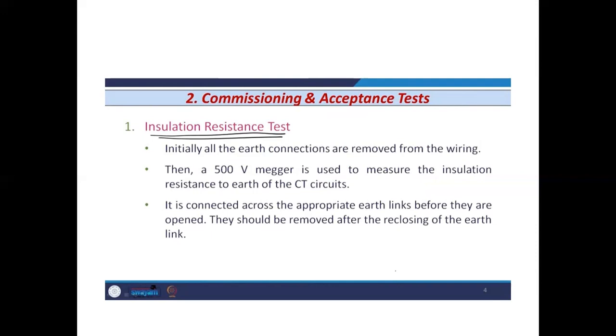Insulation is very important for the protective devices and the equipment. If proper insulation is not provided, it may cause electric shock to the operator, so proper insulation is to be provided. Initially, all the earth connections are removed from the wiring. Then a 500-volt megger is used to measure the insulation resistance to earth of the current transformer circuits, the CT circuits.